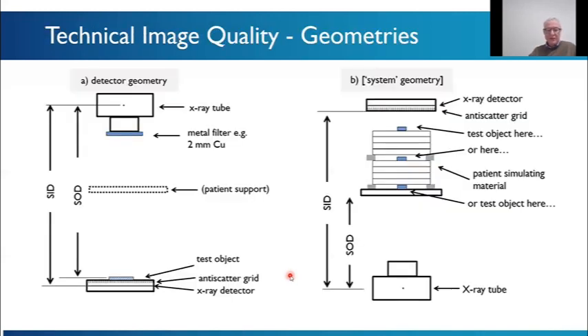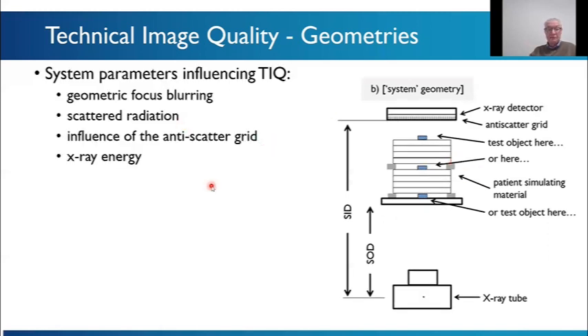So when we come to measuring technical image quality, you have a choice of 2 geometries, and the protocol describes this, either of these geometries is described. It's not very well put, sorry. We would focus on this one because this includes a lot of aspects of the system that will influence the technical image quality. It will include geometric focus blurring, because your targets are here and will be subject to focus size and focus motion blurring if the object is moving. Scattered radiation, so how good is your grid? Influence of the anti-scatter grid, I just said that. And then the X-ray energy that you're using. So high energy tends to reduce the contrast.